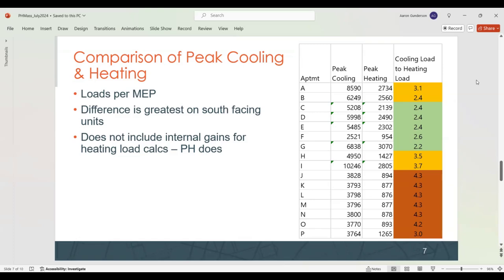2.5 to 4 times higher. The cooling loads are 4.5 times higher sometimes than peak heating. If you actually look at the way heating loads work in a passive house building, those peak heating loads would be much lower. So you're talking 5 to 6 times higher cooling loads to heating loads in these buildings. And I'm going to get into this a little bit later, but that affects comfort, it affects efficiency, it affects control.